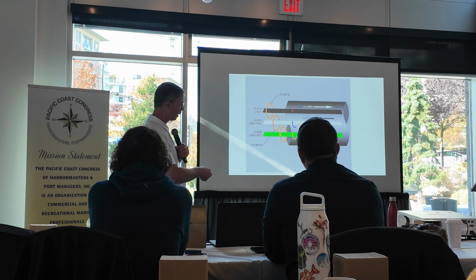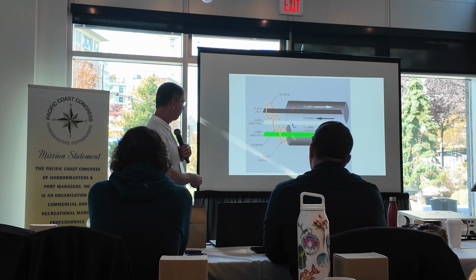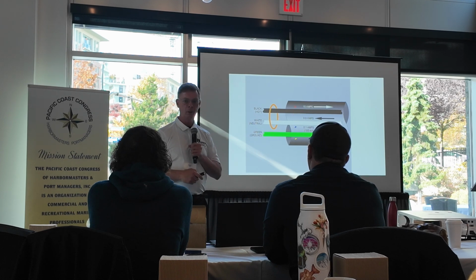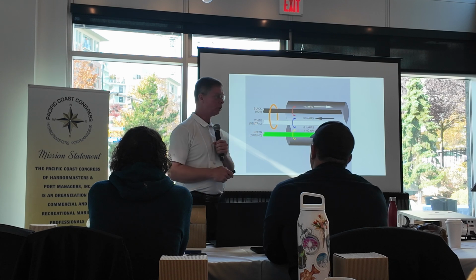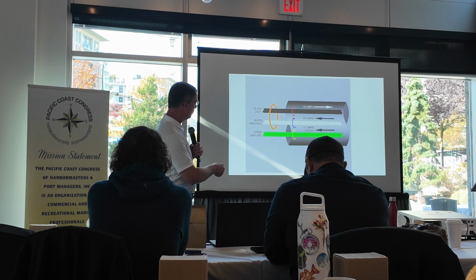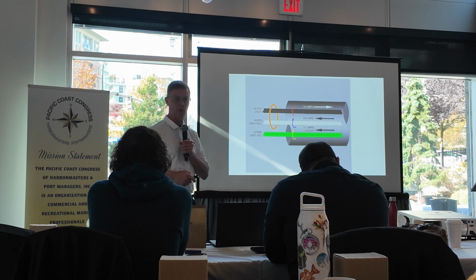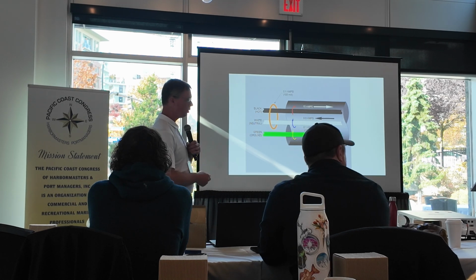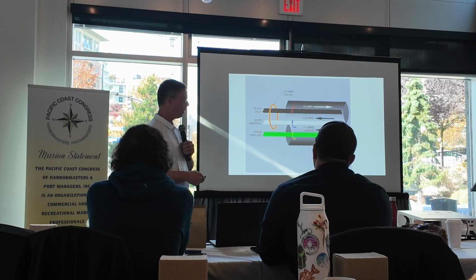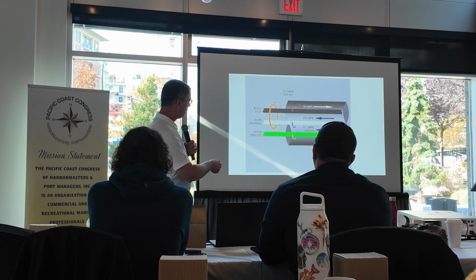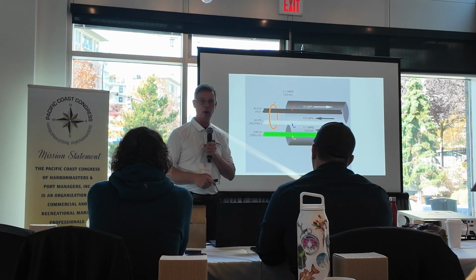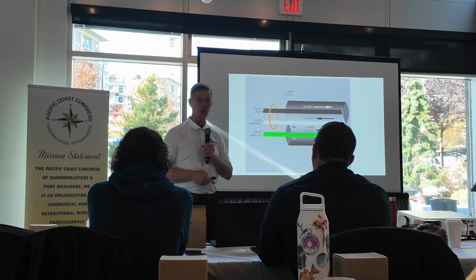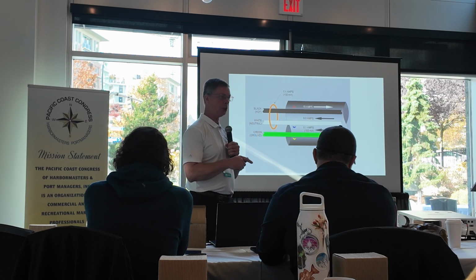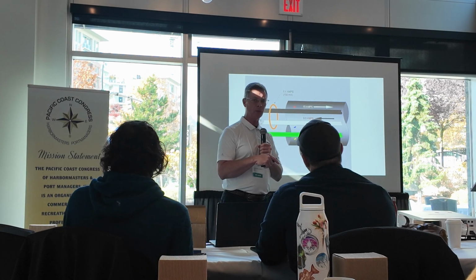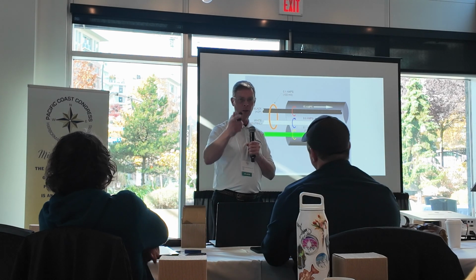Say I've got a balanced system. So I have 0.1 amps on the green wire, but if we were to clamp around both of those, what would I read? I read 0.1 amps, because it's the differential: I've got 10 amps worth of magnetic field here, but only 9.9 amps worth of magnetic field there, so I read 0.1 amps, which is actually the 100 milliamps. So that is the CT that's measuring the differentials of those magnetic fields, and that's how ground faults are measured through all equipment.